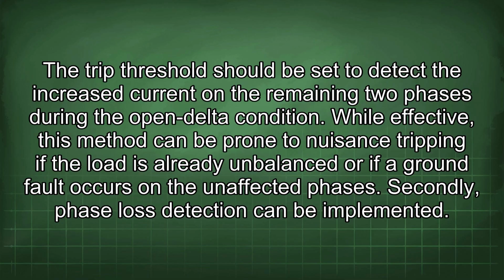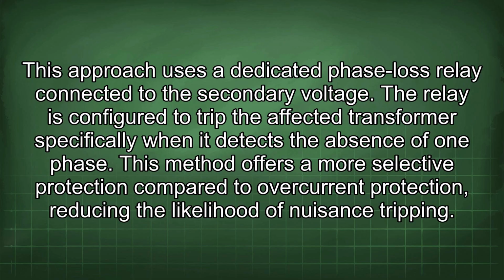Secondly, phase loss detection can be implemented. This approach uses a dedicated phase loss relay connected to the secondary voltage. The relay is configured to trip the affected transformer specifically when it detects the absence of one phase. This method offers a more selective protection compared to overcurrent protection, reducing the likelihood of nuisance tripping.